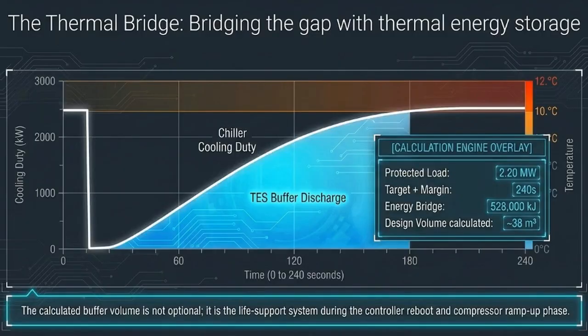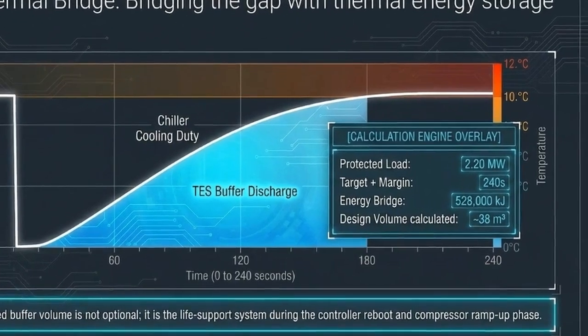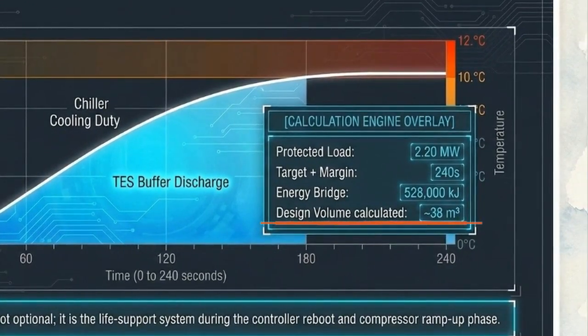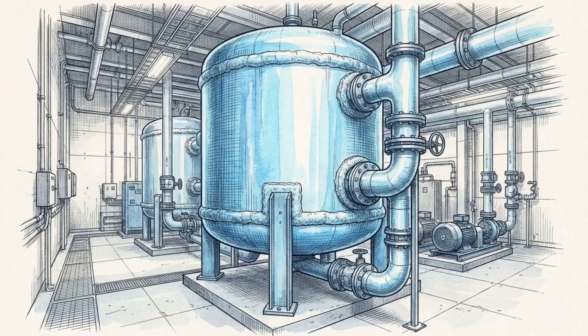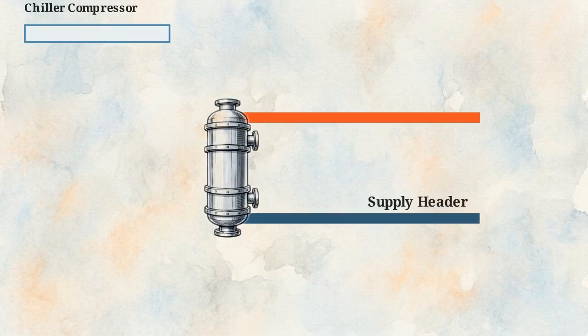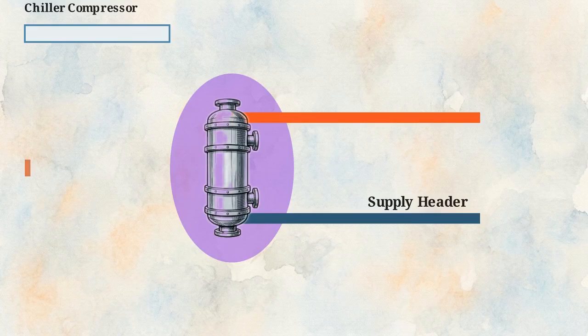Returning to the thermal bridge graph, we see how the facility survives while compressors load. The blue zone represents thermal energy storage discharging into the system. The engineering overlay calculates roughly 38 cubic meters of storage is required to bridge this specific energy gap. This TES tank acts as the thermodynamic bridge. It injects a precisely calculated volume of pre-chilled water directly into the supply headers, actively absorbing the IT heat while the mechanical chillers are still catching up.